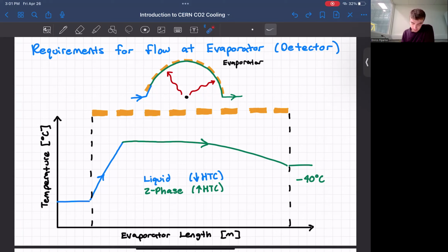Say we enter the evaporator in liquid CO2, and right after the beginning of the first silicon sensor, the heat from the silicon sensor is absorbed by the refrigerant. As a result, the liquid CO2 increases in temperature until it reaches the boiling point. Right after the boiling point, we are boiling, or in two-phase. And it's important to be in two-phase along the evaporator. One, because of its isothermal properties, that is, the temperature difference between the first and last silicon sensor is minimal. And two, because two-phase has a much higher heat transfer coefficient compared to liquid. Heat transfer coefficient can be thought of as the efficiency at which heat from the silicon sensor is absorbed by the refrigerant.